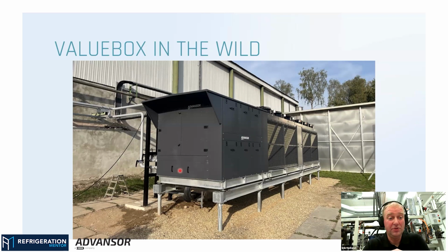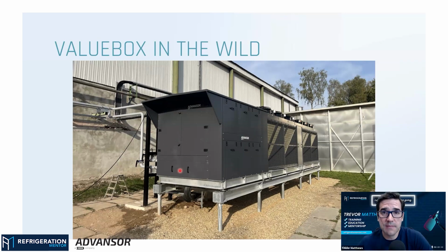But of course we see from time to time that we come up and the pump system is not really calibrated correctly, or it's not dimensioned correctly, so it's the wrong size of pump for the system. It's either way too big or way too small, and that creates some delays, of course. Yeah.